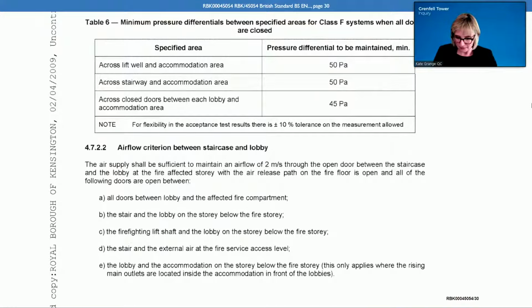Did you ever consider the fire resistance of the ductwork, either the builder's work shafts going up both north and south, or the level 2 ductwork? Did you ever make an assessment of that and consider its fire resistance? This was really marked up on the architect's plans, the shafts were marked as fire-resisting shafts. So we took that. So did you just take that at face value? Did you ever actually work out what standard those ducts satisfied when you were approving the system?